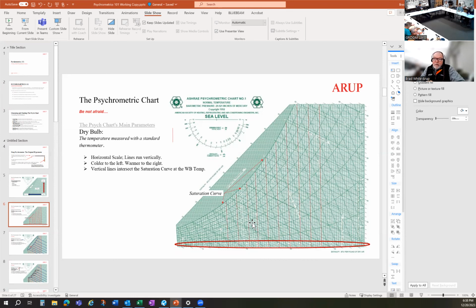And I found vapor -- sorry, Ed. So the vapor pressure is driven and will change with temperature, driving the moisture whichever way it's going to go. It changes more with moisture -- as I recall, it changes more with the quantity of moisture in the air, and less so with temperature. But I've got the gradient on that. Actually, I have a gradient calculator for it.